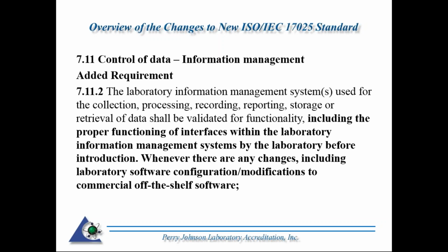The laboratory information management system used for the collection, processing, recording, reporting, storage, or retrieval of data shall be validated for functionality, including the proper functioning of interfaces within the laboratory information management system, by the laboratory before being introduced, and whenever there are any changes, including laboratory software configuration modifications to commercial off-the-shelf software. So this is software validation.